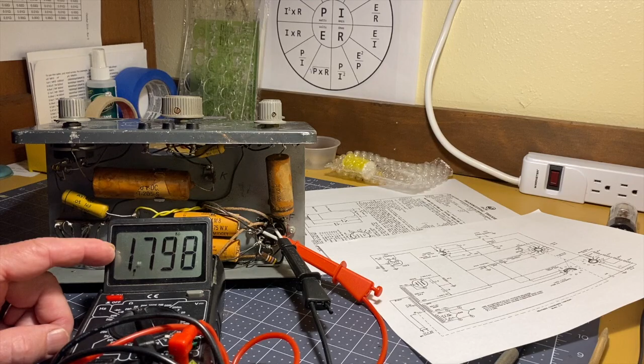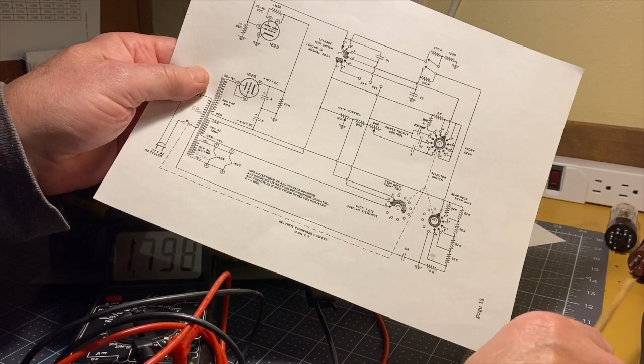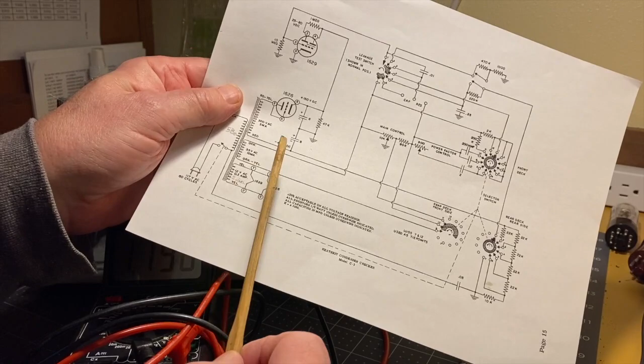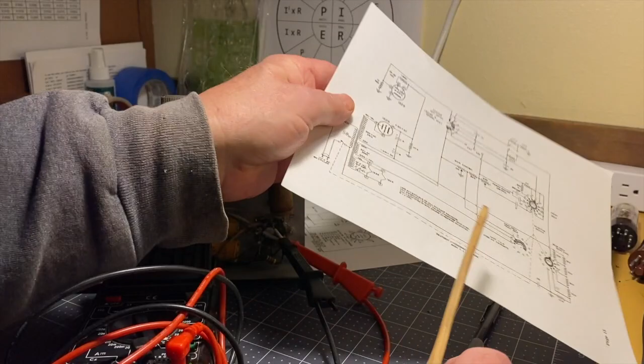1.79K, which again for a high voltage winding makes a lot of sense. There's a lot more wire in the high voltage winding to create this 500 volt AC secondary than there is to create a 12 volt AC secondary. So this is 2.6, and this is 1.8K right here. I'd say that's good. Make note of that.